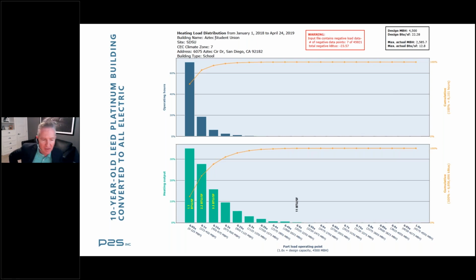This slide is an example of a retrofit of a 10-year-old LEED Platinum building that was converted to all electric. We designed the original building that was LEED Platinum, but this is very typical of what we're seeing, at least in the Western United States, when we look at heating load profiles. 1.0 on the bottom being the size capacity that was installed in the building. This one happened to be 22 BTUs per square foot. And what you see over here on the left-hand side on the green bars is the distribution of the actual load for the percentage of operating hours of that system. So you'll see just those two left bars make up over 60% of the operating hours, at less than 2.2 BTUs per square foot. That's extremely low. I mean, we're talking about less than 10%.